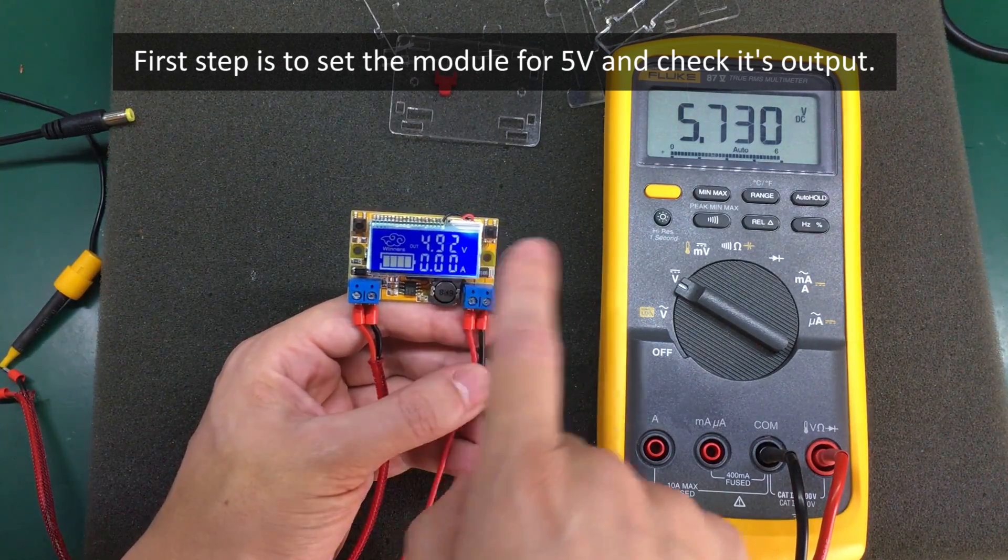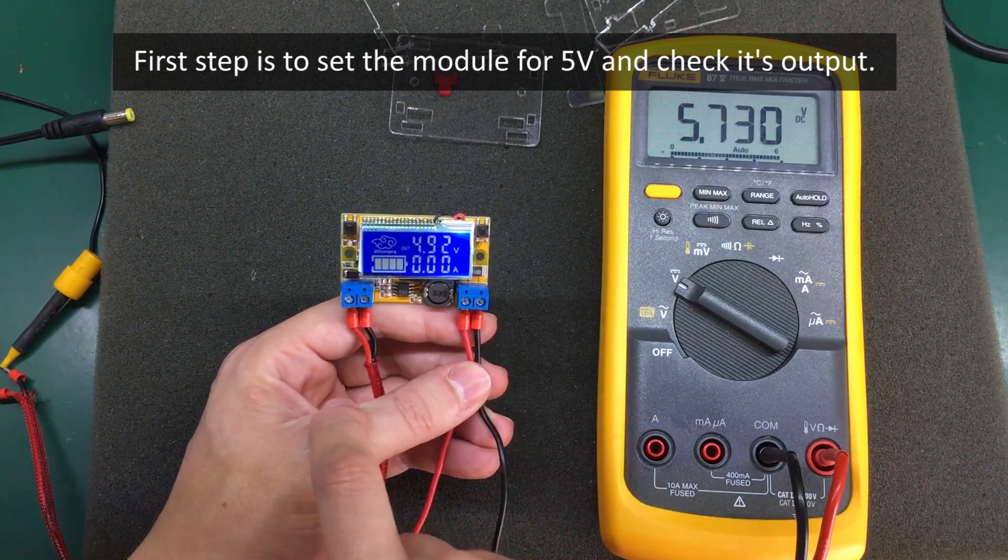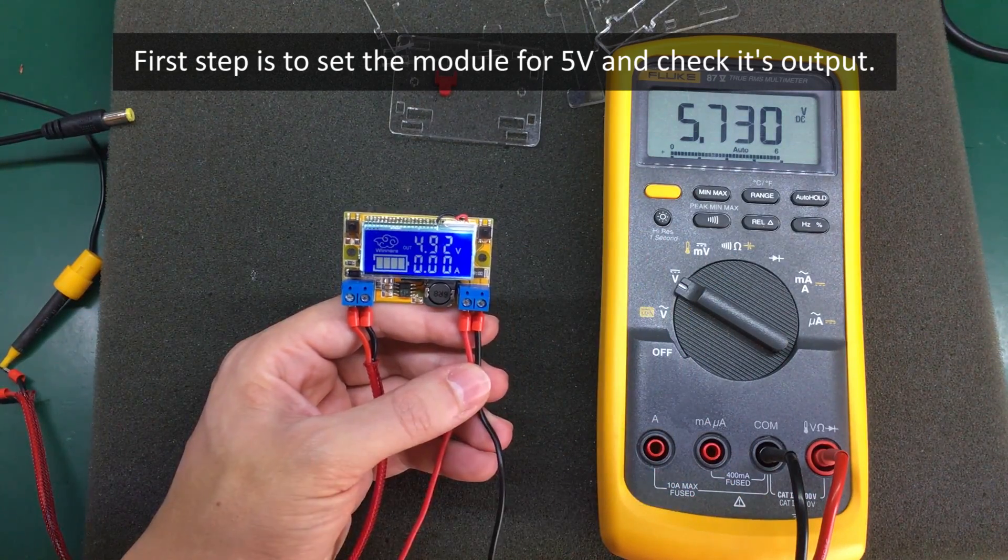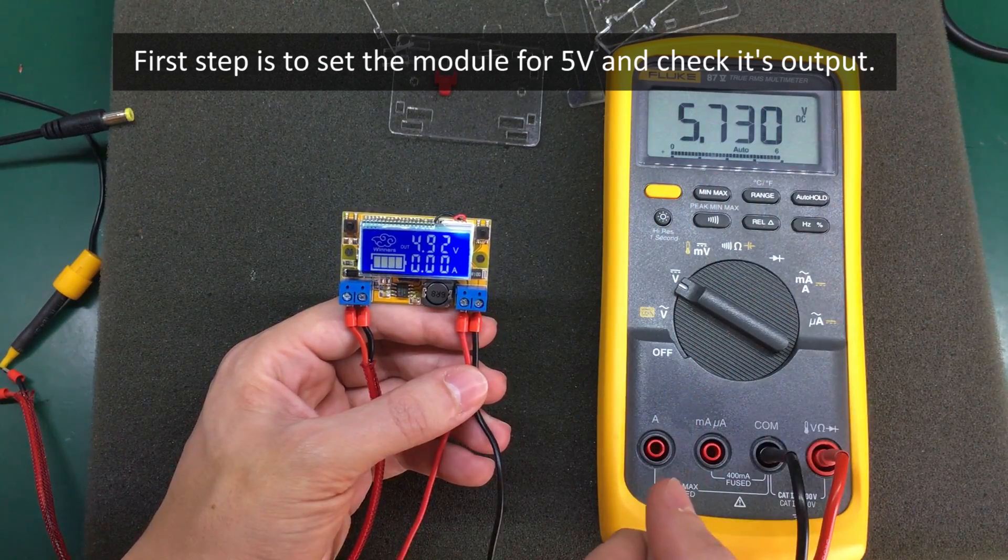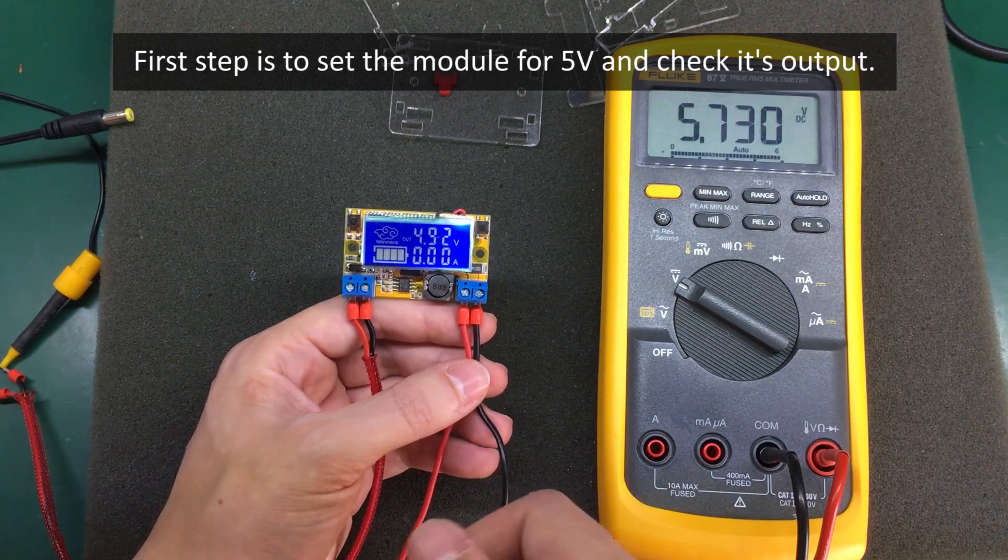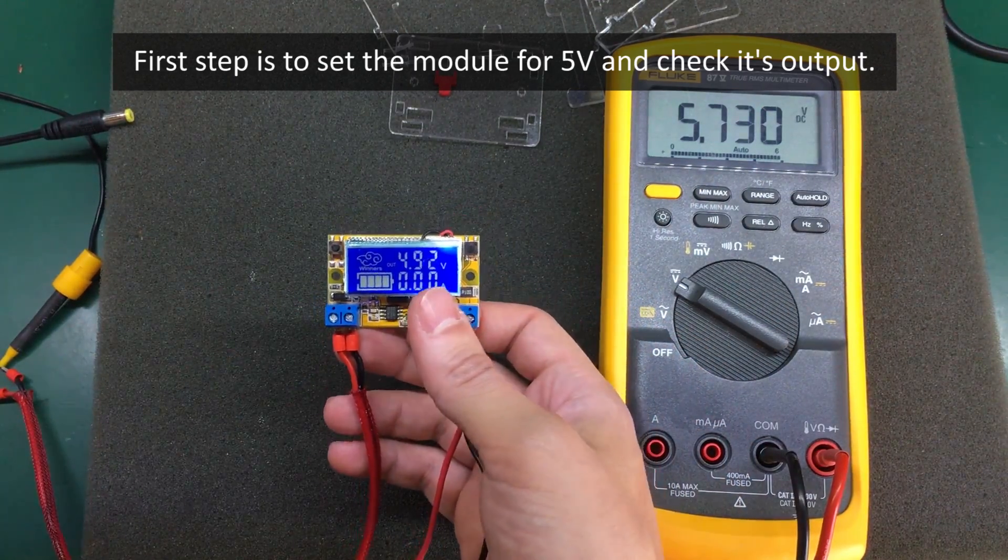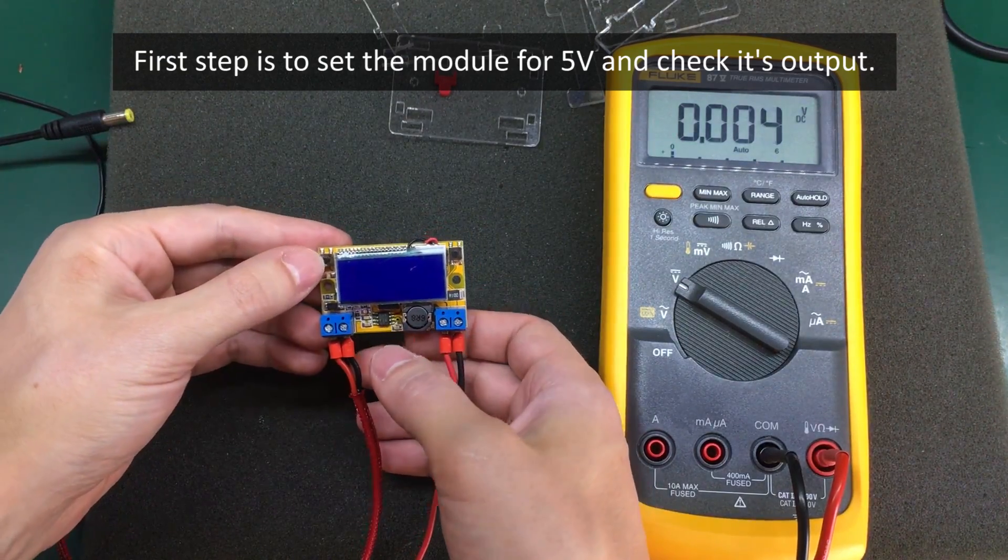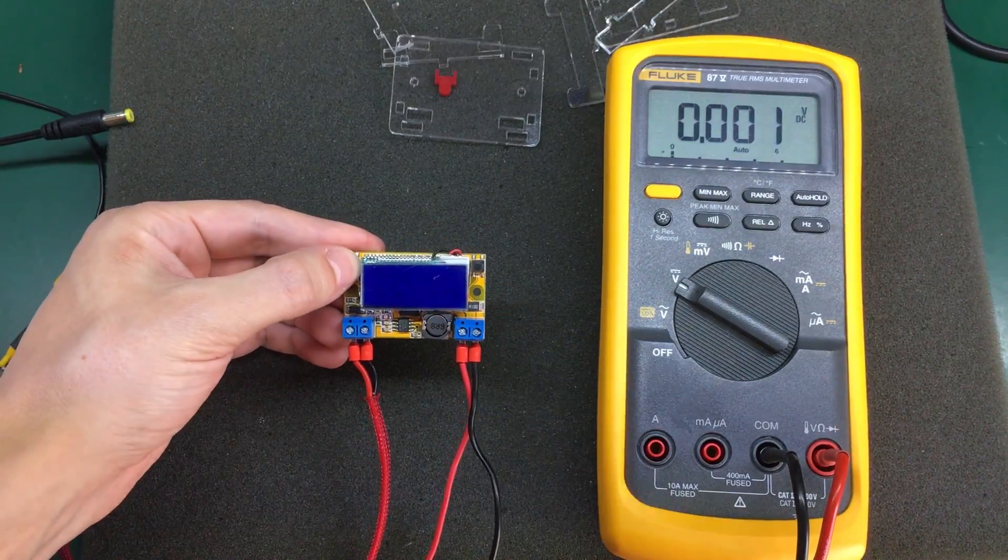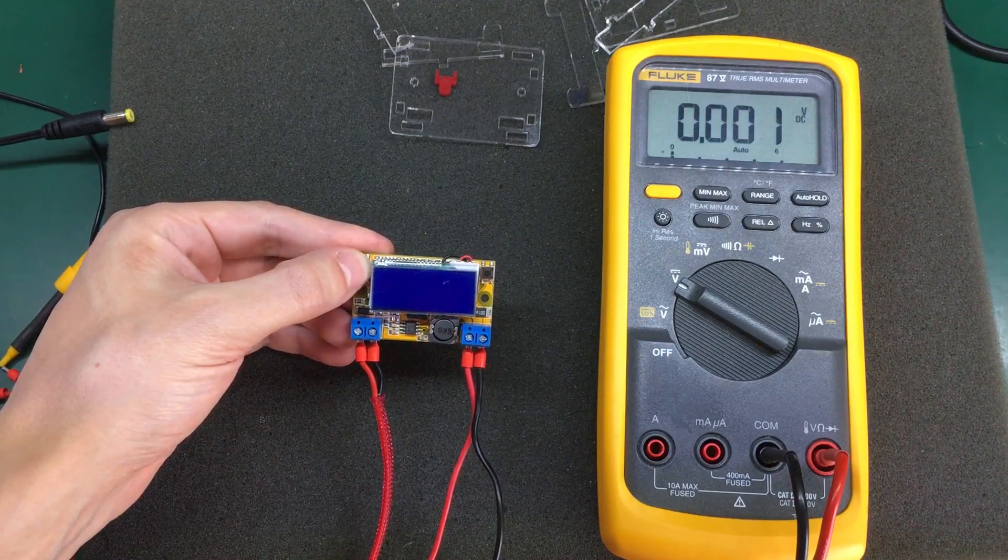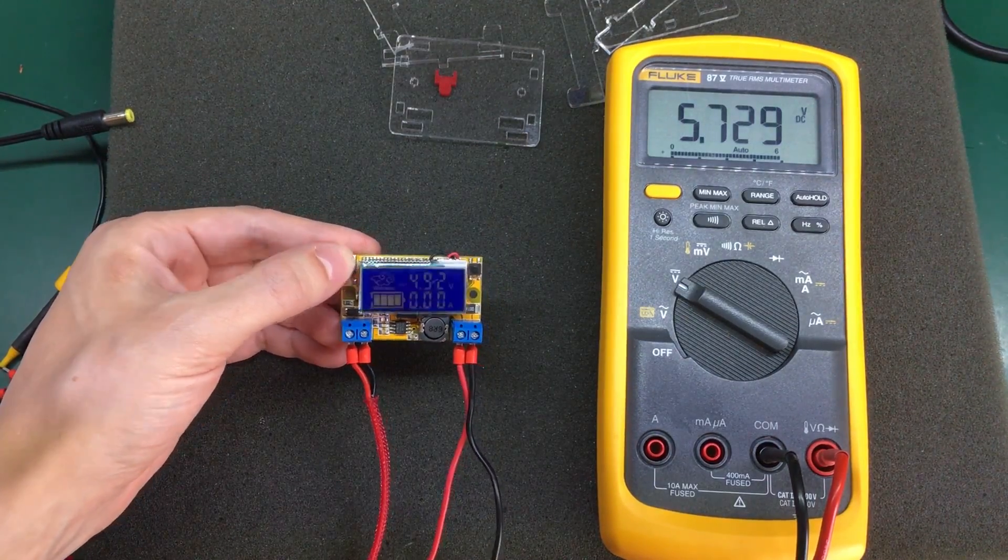So in this case I have induced a larger error so that we have something to calibrate. We have about 700 millivolts error and this is the procedure. Power must be turned off. The left button must be kept pressed and you apply the input power to the module.